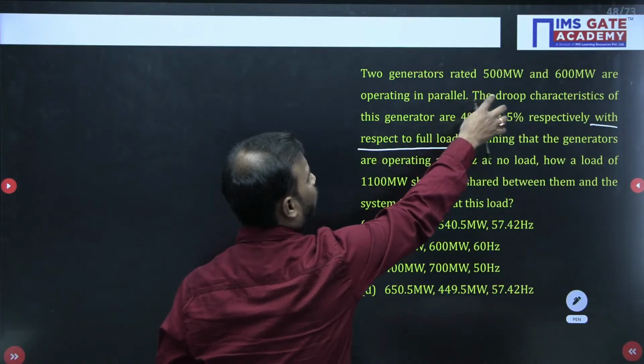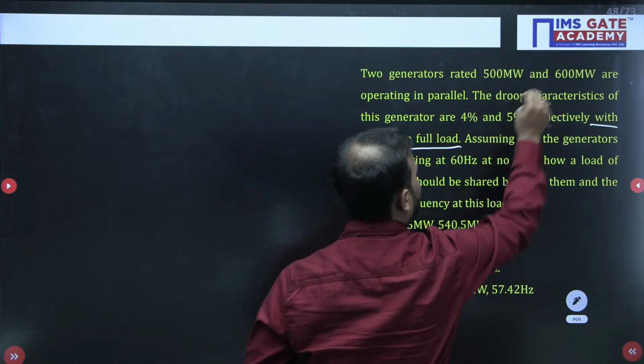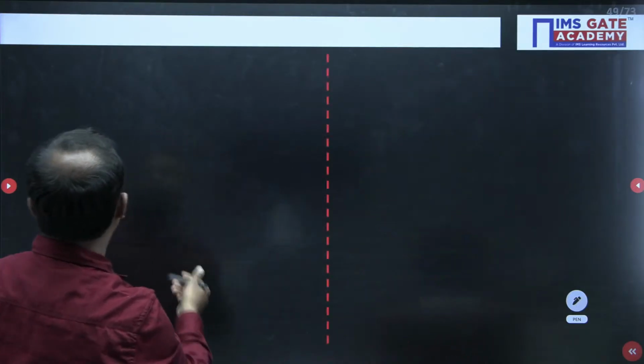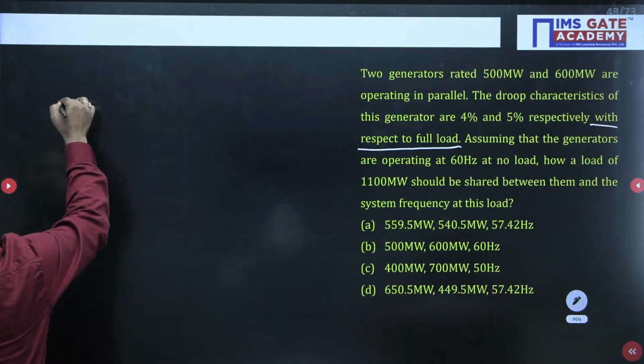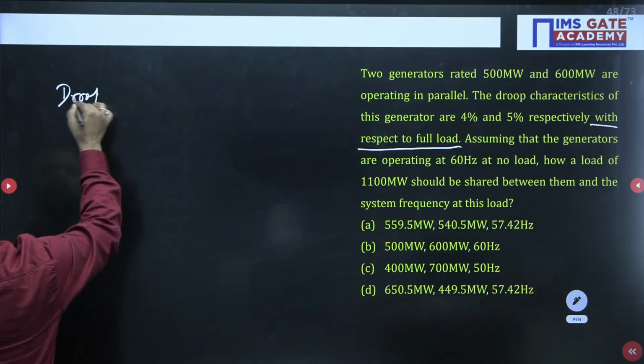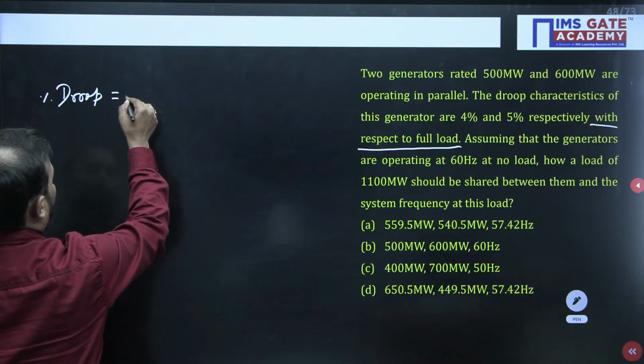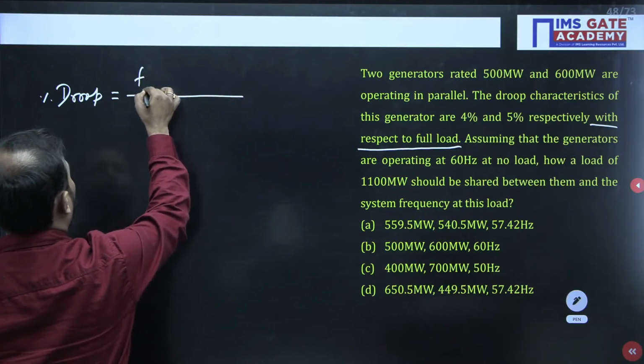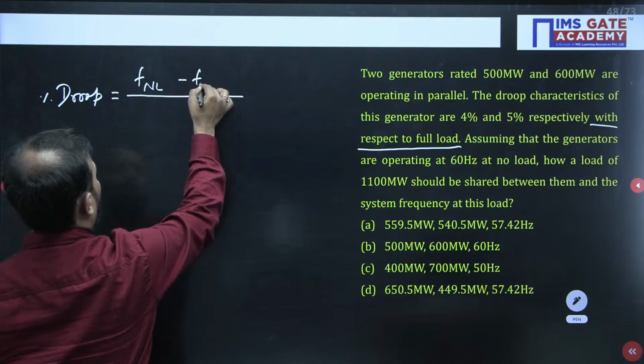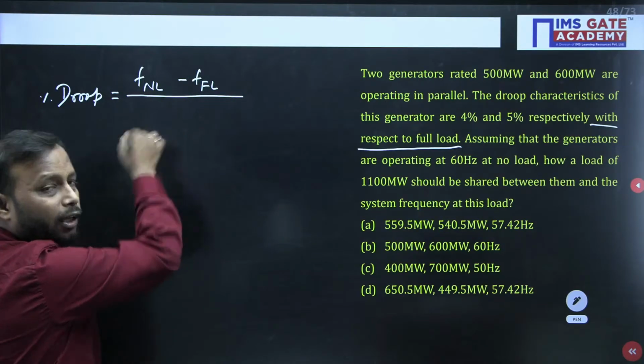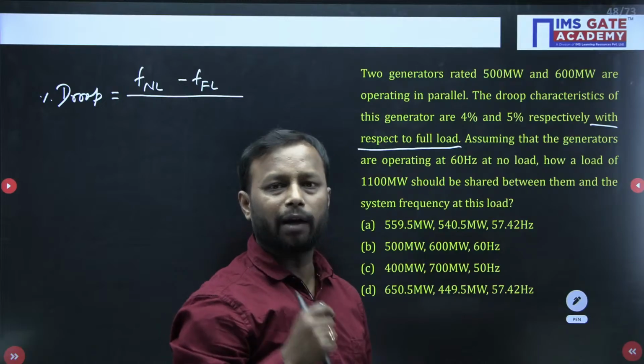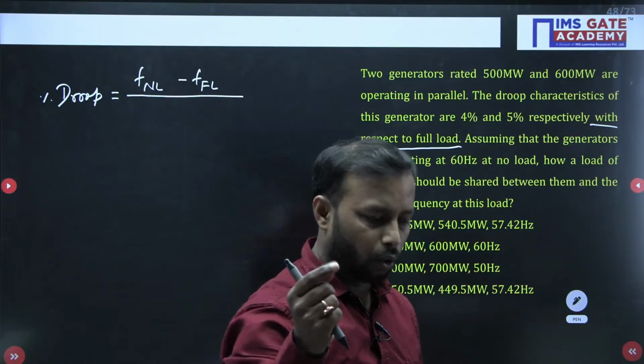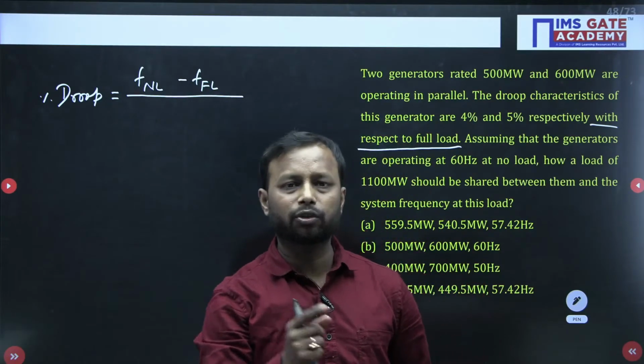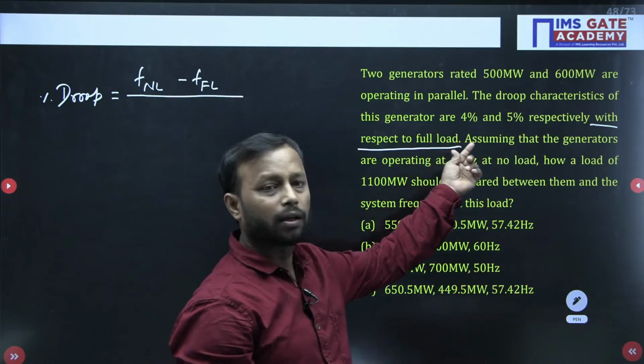Look here, 4% for this particular load and 5% for this particular load is given. So what is the formula for droop, or percentage droop? It is change in frequency from no load to full load. In the denominator, either full load or no load can come, it depends on how the examiner is defining the droop.